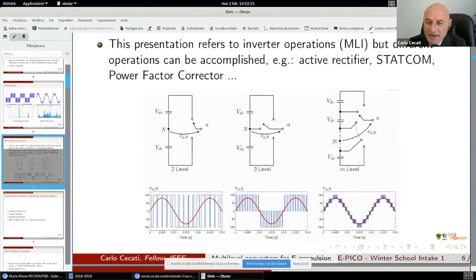They can be easily replaced, their efficiency is much better, and they are also safer, both because they are smaller and because each one has a low voltage. In all cases, the output voltage stays at the same level, so the converter and then the motor are supplied by switching from 0, or from minus to plus. In a multi-level inverter, we have very low voltage steps, and increasing the number of levels decreases the amplitude of each step.